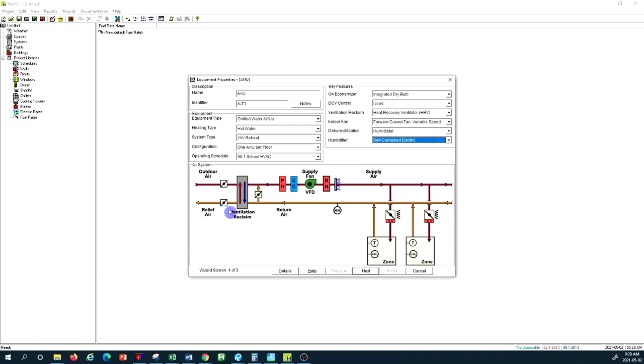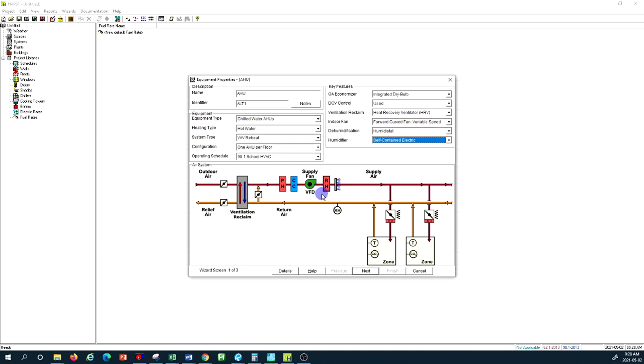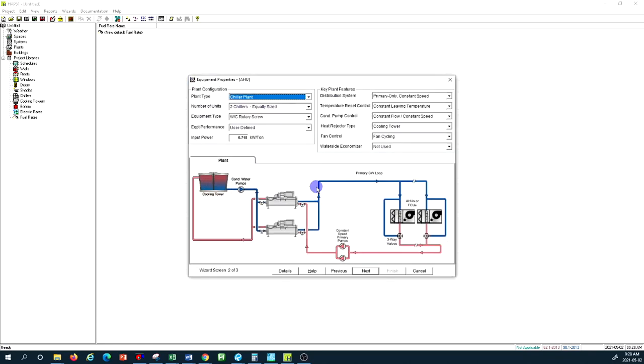We have VAVs serving every zone with primary air supplied through the air handling unit, which also includes outdoor air. Relative humidity sensors evaluate humidity levels, and more humidity is injected into the supply air stream as needed. There is a preheating coil, cooling coil, and a reheat coil — if you control humidity, you may need to reheat the air to bring the temperature up for precise humidity control.